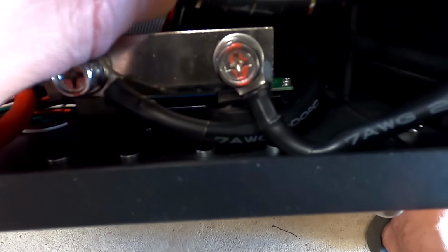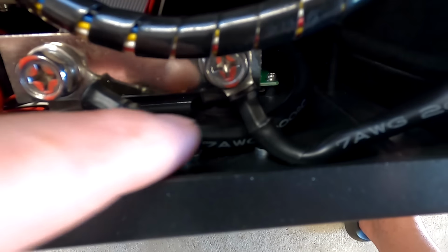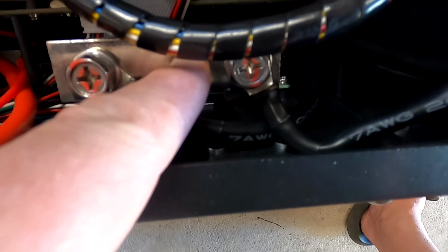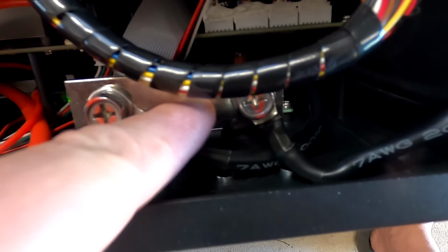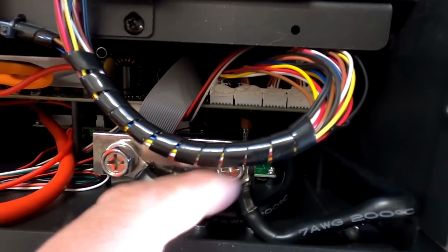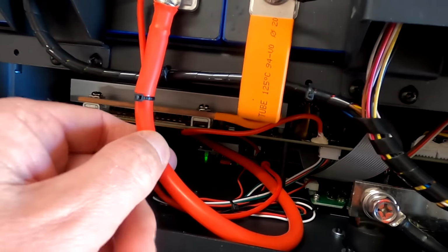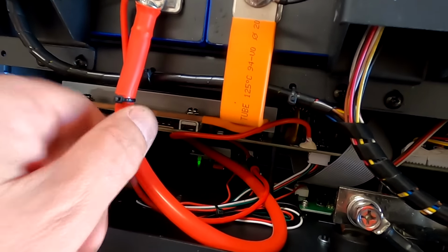Always. Well, here with the negative, they have actually used a 7-gauge wire, but 2 of them to go from the terminal, or to come from the BMS back to the terminal. And there's no actual square millimeter comparison to a 7-gauge wire. This is between 16 and 10 square millimeter. But at least we've got 2 of them. So this should give us at least a 100 amp current carrying capacity. So we maybe have 120 amps here on the negative side, but only 80, 90 here on the positive side. So there's a bit of an inconsistency.